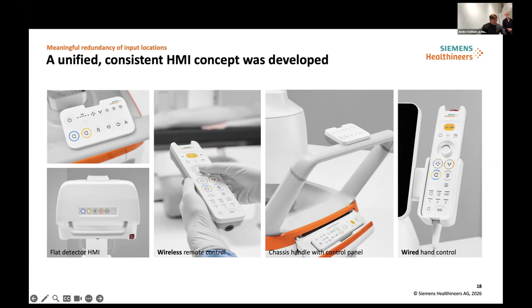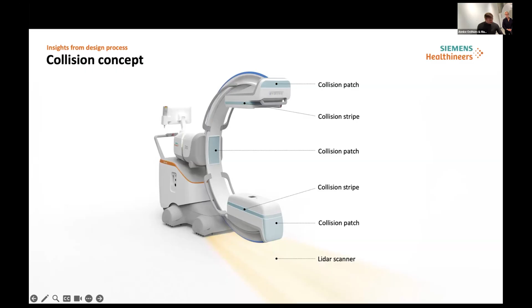As we talked about braking the device and avoiding collisions, the image shows silicone patches or strips on the C-arm highlighted in light blue. If the device contacts anything using these silicone areas, it stops immediately, and the user must steer the device out of the collision. The LiDAR sensor, shown in yellow, similar to those used in cars, prevents accidents with people crossing the device's path. It enables users to drive at a higher speed when moving the device to an operating room or back to its parking position in the hallway. And the LiDAR sensor ensures that the device performs sudden braking maneuvers if needed.